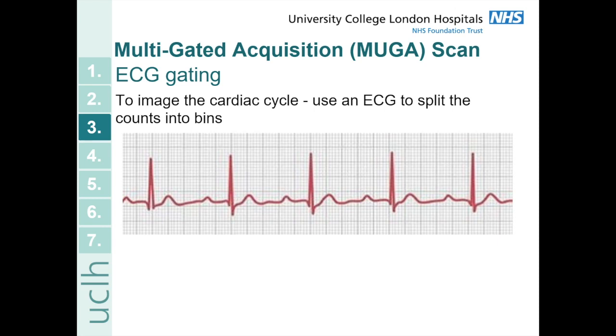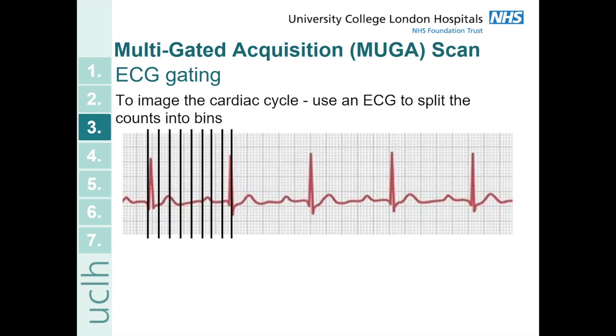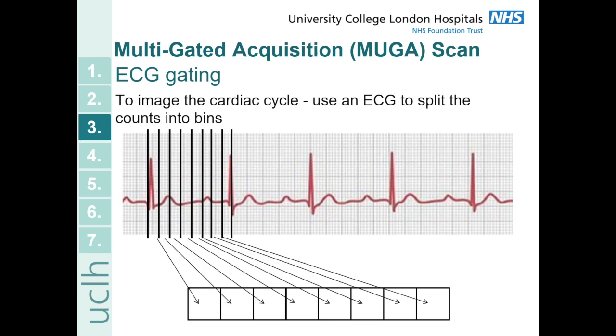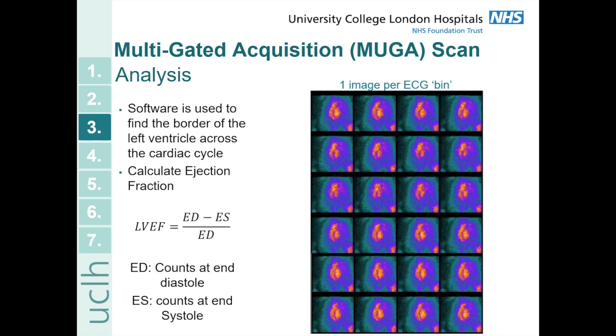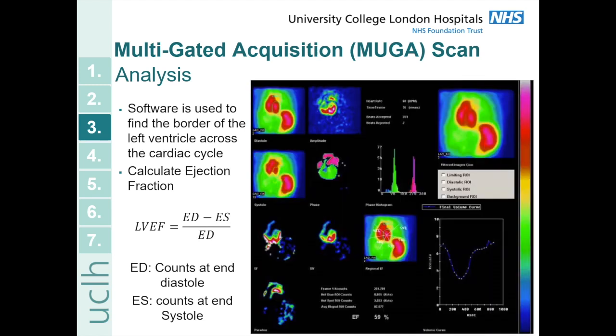ECG-gating is used so that we can image across the cardiac cycle. We use the ECG signal to split the counts that we're recording into separate bins, dividing the cardiac cycle into bins. Counts recorded within each time frame of the cardiac cycle are assigned to the correct bins, and for the next cardiac cycle the same bins are assigned. This means we can accumulate counts within the bins to produce an image across the 10 minutes, averaging across the 10 minutes for each of those bins. To analyse the MUGA scan you use software to find the border of the left ventricle across the cardiac cycle and calculate the ejection fraction using counts at end diastole and systole.